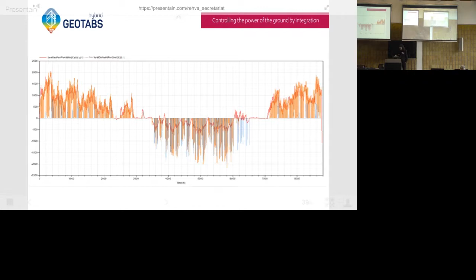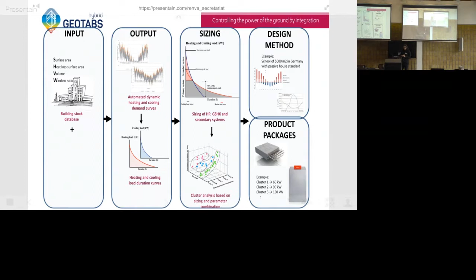Based on that, we're sizing the secondary system, using more traditional methods based on load duration curves to also size the ground source heat exchanger and the heat pump. From that, we're working towards market-ready product packages and a design method that is easy to follow by an unexperienced design engineer. And so, next is Irje.